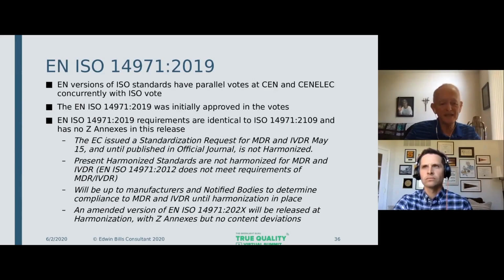However, on May 15th, they did issue a standardization request for the MDR and the IVDR, and that includes both 13485 and 14971. Until those standards are updated by CEN and CENELEC, and the results are published in the official journal, they are still not harmonized. The present harmonized standards are not harmonized for MDR and IVDR. They are only harmonized for the directives, so they don't meet the requirements of the MDR and IVDR. So it's up to you as a manufacturer working with your notified body to determine compliance to the MDR and IVDR.